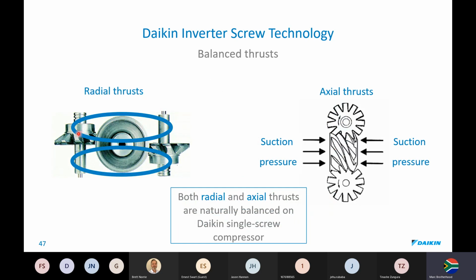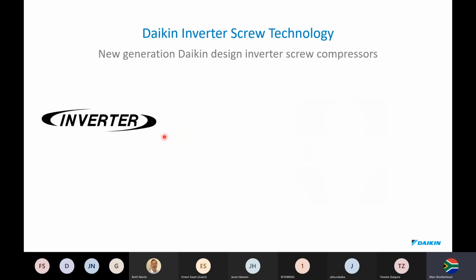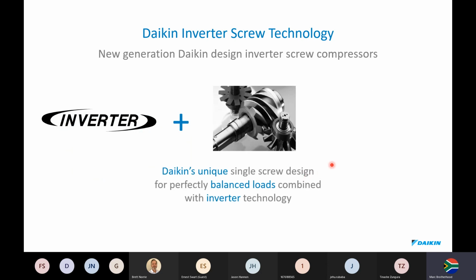Also, as I said to you, these gate rotors oppose radial thrust. So radial thrust is thrust that throws out at 90 degrees to your angle of rotation. And axial thrust is something that is thrust in the line of rotation. So both radial and axial thrusts are naturally balanced with our Daikin screw compressor. And we only have 6 bearings in this. If you had to compare the opposition, some of them have up to 30 bearings in their compressors to balance loads, primarily to balance radial forces, which means a lot of noise in those bearings and a lot of wear metals in the oil.